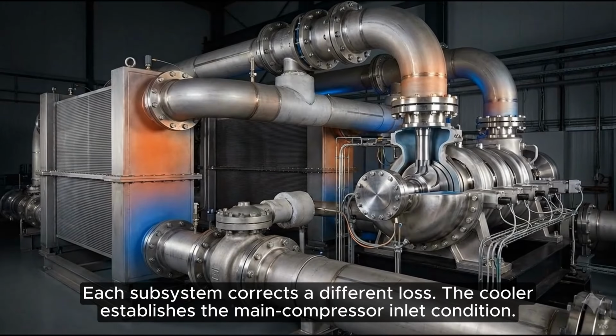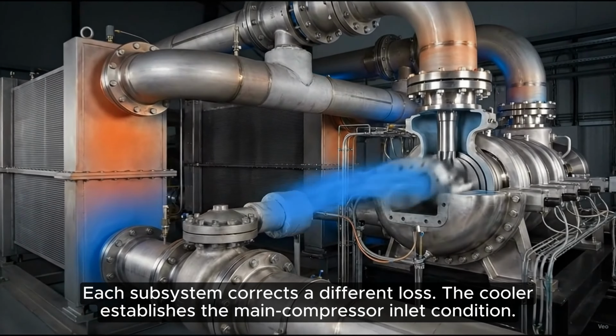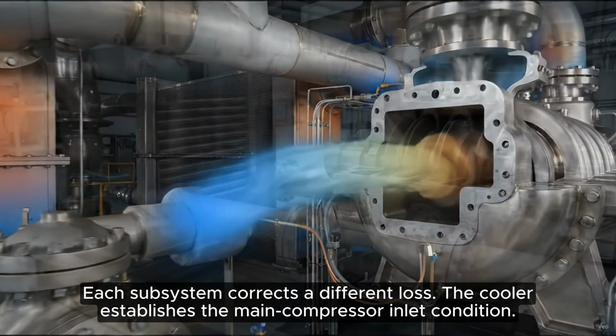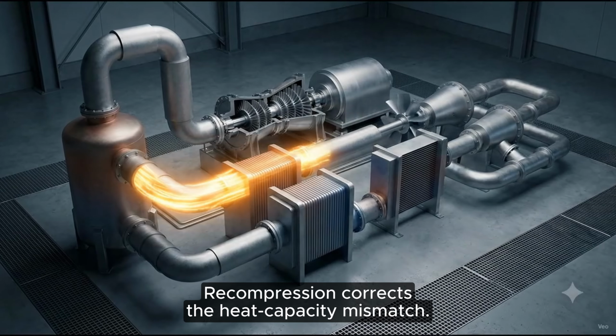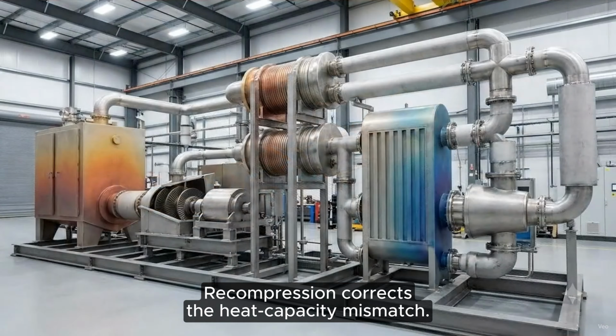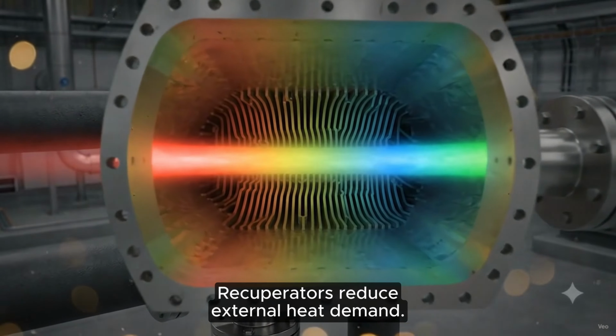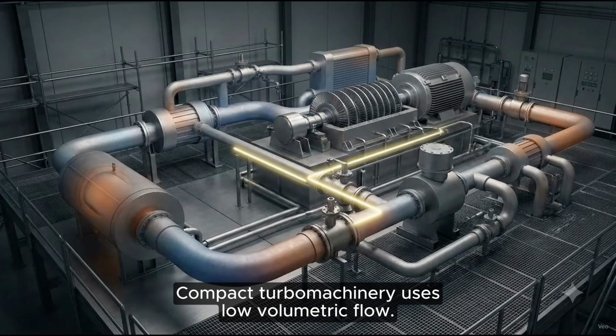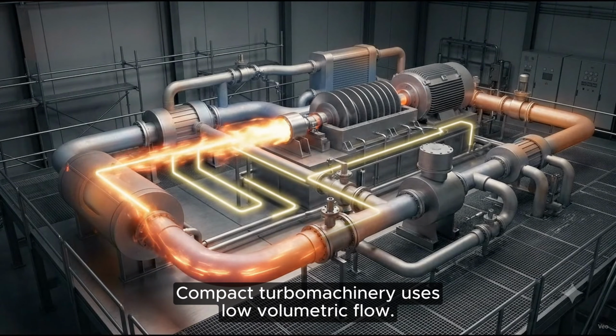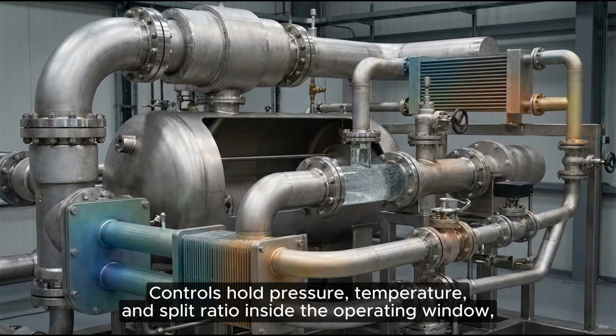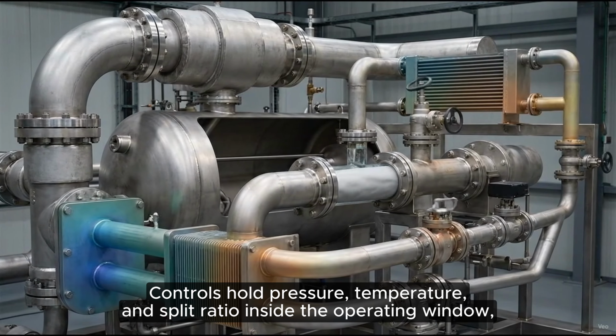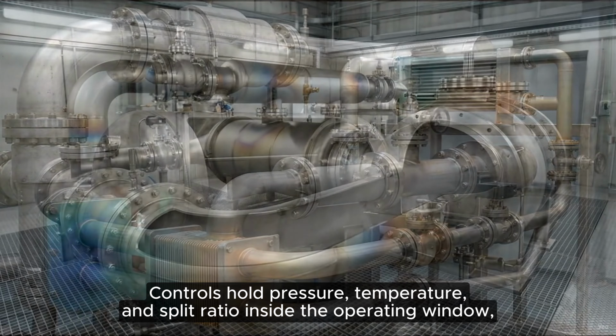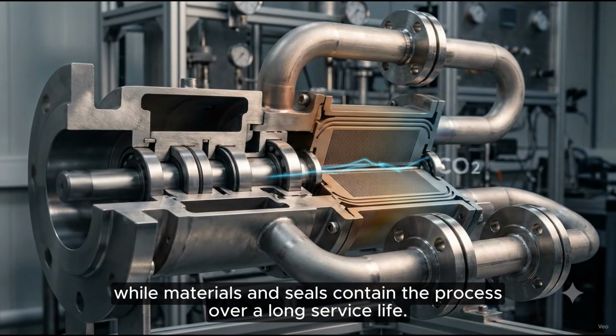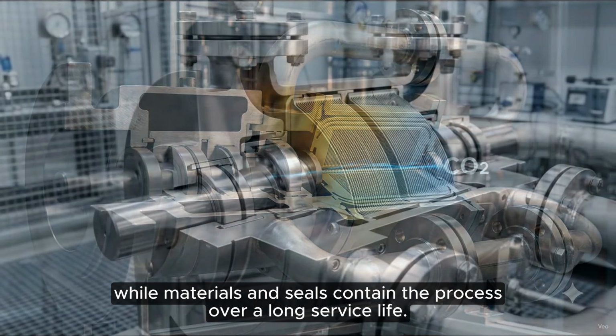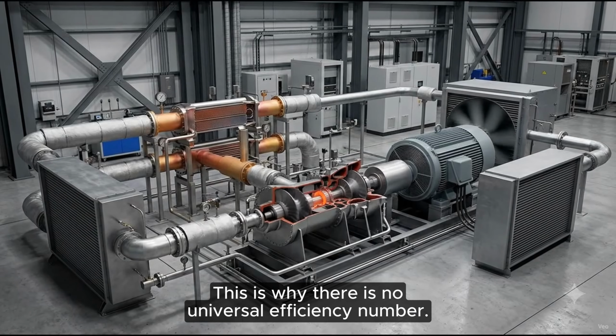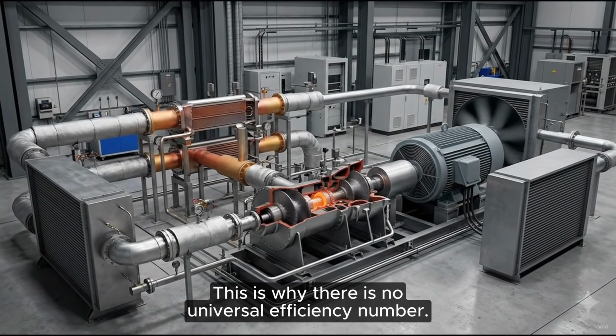Each subsystem corrects a different loss. The cooler establishes the main compressor inlet condition. Recompression corrects the heat capacity mismatch. Recuperators reduce external heat demand. Compact turbomachinery uses low volumetric flow. Controls hold pressure, temperature, and split ratio inside the operating window, while materials and seals contain the process over a long service life. This is why there is no universal efficiency number.